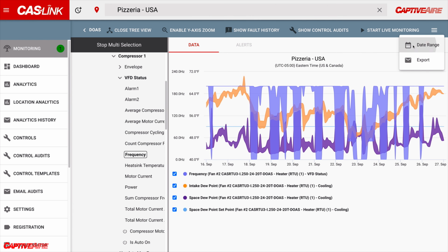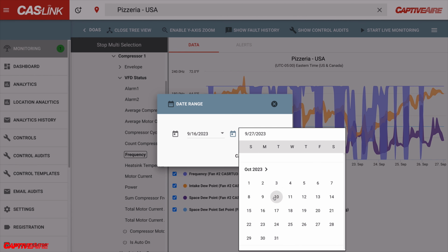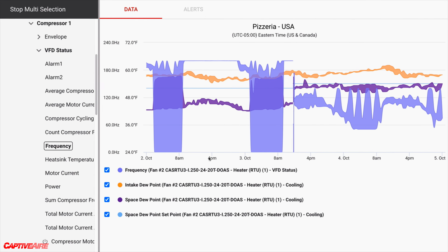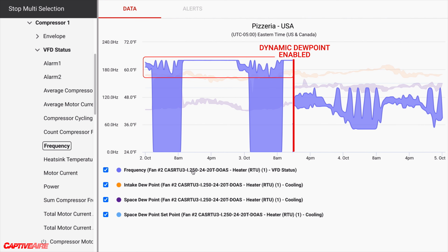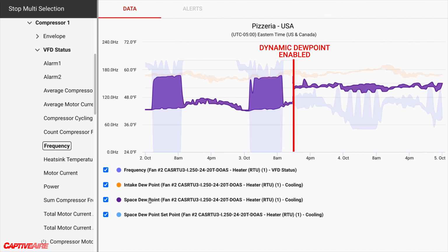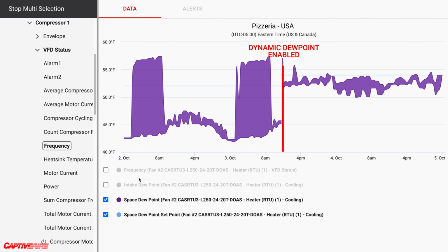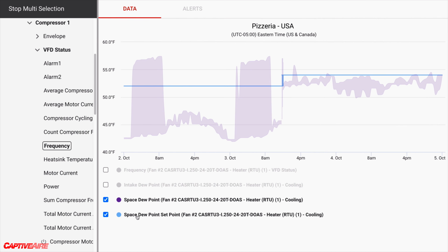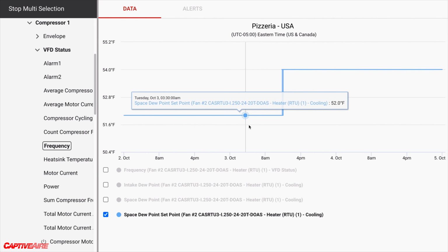We'll go into why this feature wasn't originally enabled later in the video, but for now, let's look at what happened when we did activate dynamic dew point. Already we can see it's starting to zoom in. This compressor speed, which was sitting at max speed, is now running closer to 50% capacity in many of these cases. And with that, you can see that purple space dew point now goes right back up. When we first looked at this, a 52 degree dew point for a kitchen is pretty low. Even if we're trying to target maximum comfort, 52 is a pretty dry kitchen.